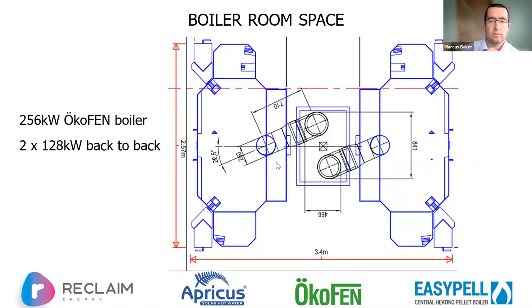So just to give you a worked example, this is from a college, and this is looking at it in plan view. And so we've got 128 kilowatts here, another 128 kilowatts there. The flues are slightly offset. They ended up actually having to bend them so they were straight. But anyway, they're as tight as can be. And so there we've got 3.4 by 2.6 giving us 256 kilowatts. So it doesn't have to be ridiculously large to get some really quite significant outputs.